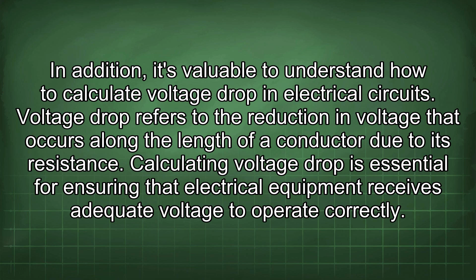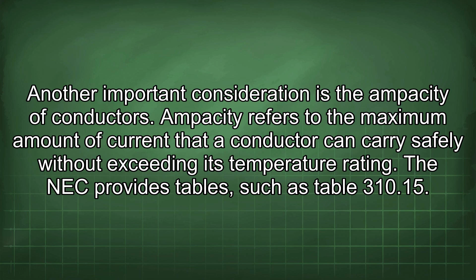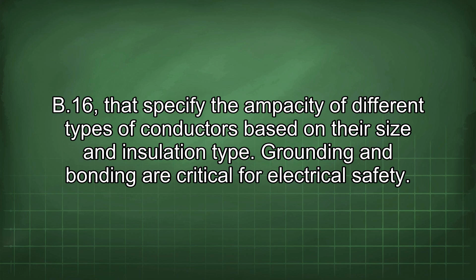Another important consideration is the ampacity of conductors. Ampacity refers to the maximum amount of current that a conductor can carry safely without exceeding its temperature rating. The NEC provides tables, such as Table 310.15(B)(16), that specify the ampacity of different types of conductors based on their size and insulation type.